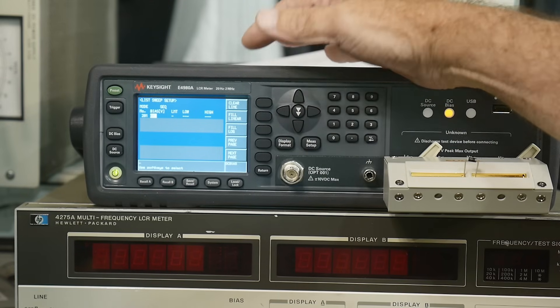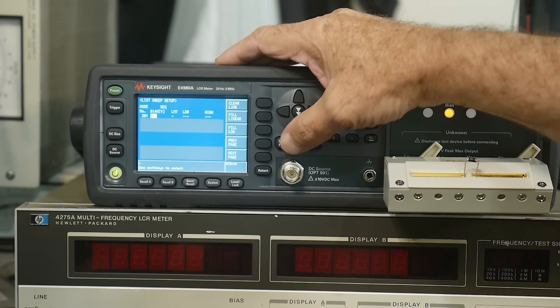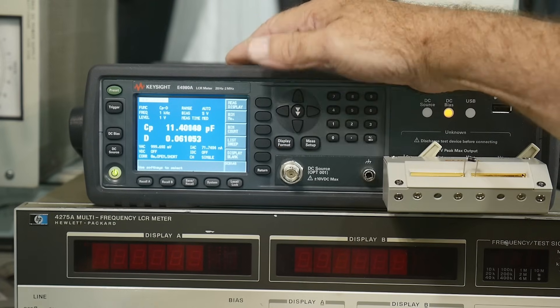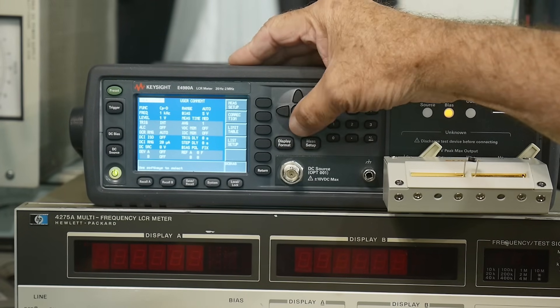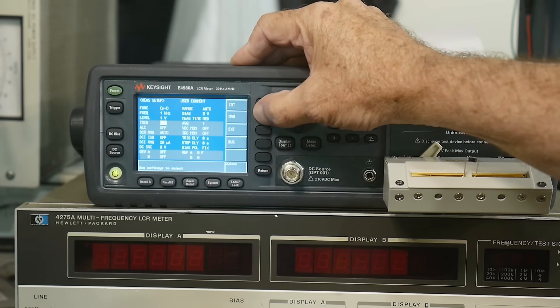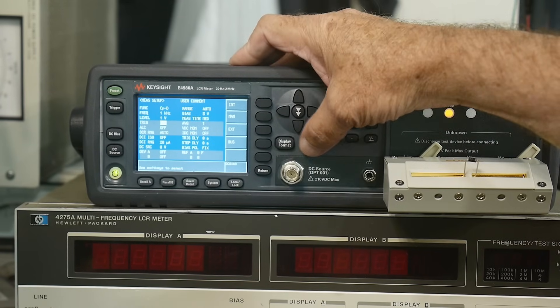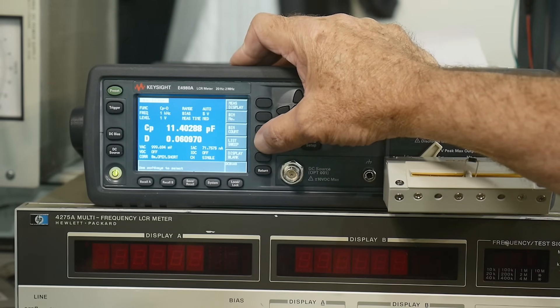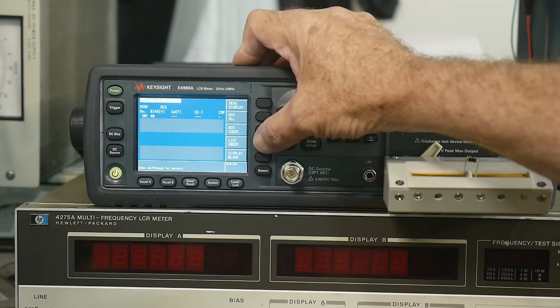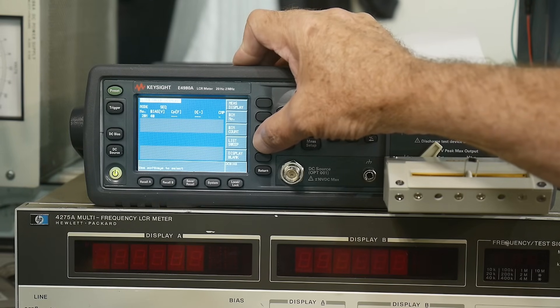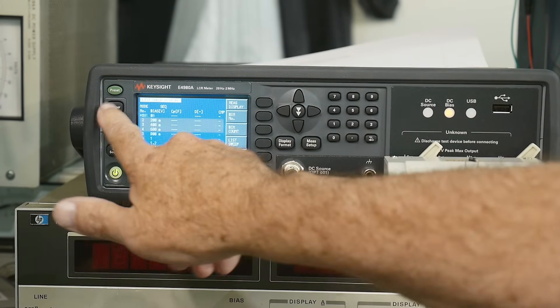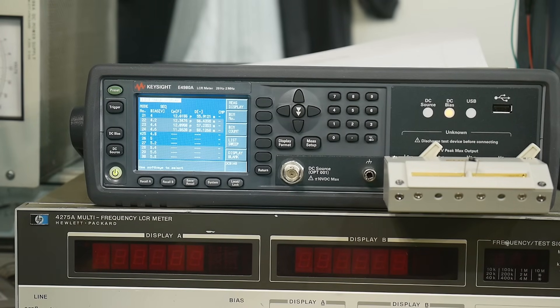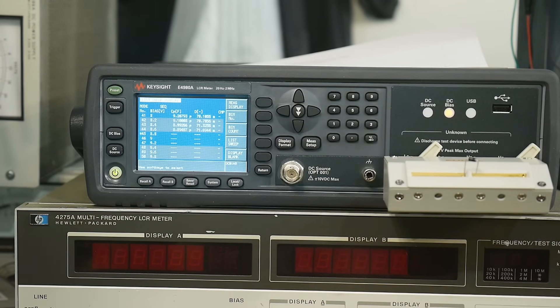All right. And the way that I do that is to do a display format. You need to first set the triggering to manual. All right. And then when you go to the measurement page, you do a list sweep. Okay.